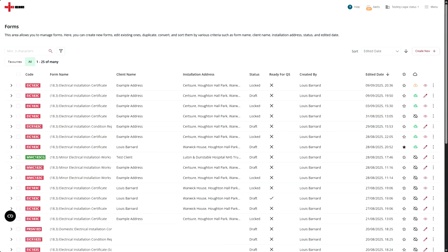Okay. We'll jump around a bit because we'll take the questions in the order and the frequency that they came in. So a lot of people are asking why we don't automatically fill in maximum Zs values for RCBOs, and that's really because, without knowing what your design is like, we're not sure whether you're using the RCD characteristic or the MCB characteristic, both methods of which are acceptable with regards to the design, and you might choose one for a particular installation reason.